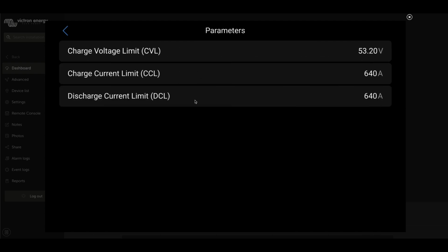Now let's look at the parameters. This is the most critical area for understanding what's happening with DVCC. That's Victron's Distributed Voltage Current Control menu. And this tool is the most critical way that Victron is going to take BMS information and make use of it in a Victron system. This charge voltage limit will set the maximum charge voltage across the system through DVCC. And this charge voltage limit is set by the battery. This is information coming directly from the battery. This isn't something that was user set. This is the battery saying, I don't want any more than 53.2 volts.